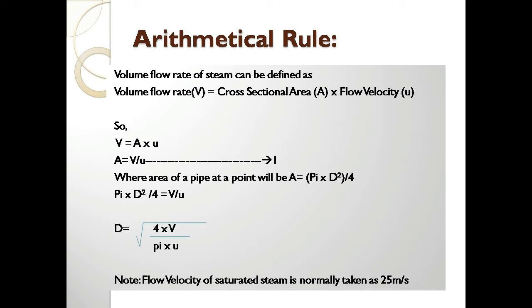We can calculate pipe size by arithmetic rule. Volume flow rate of steam can be defined as: volume flow rate V is equal to the cross-sectional area of the pipe multiplied by flow velocity. Our requirement is to calculate the diameter of the pipe, so we will transform this formula accordingly.